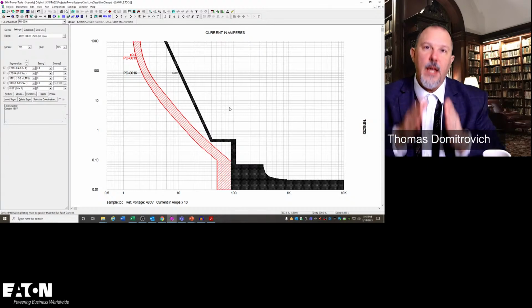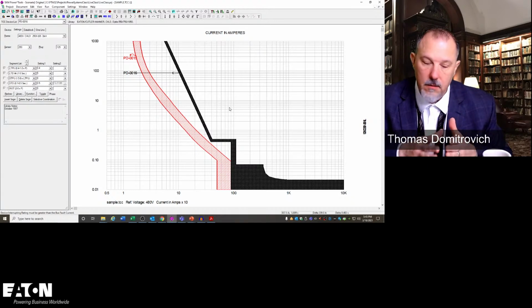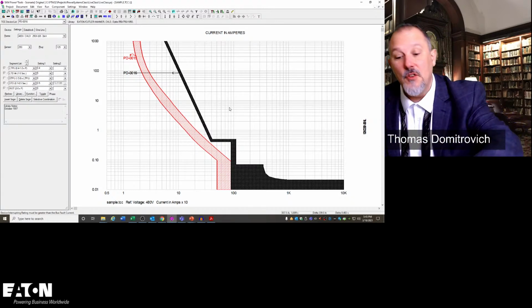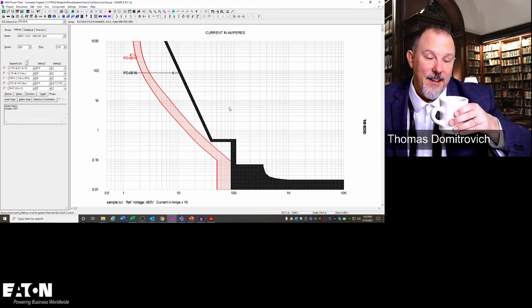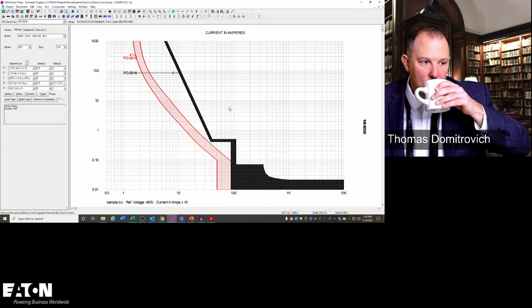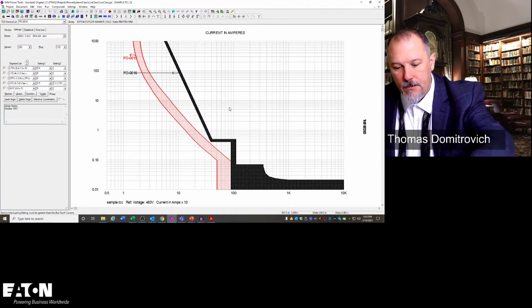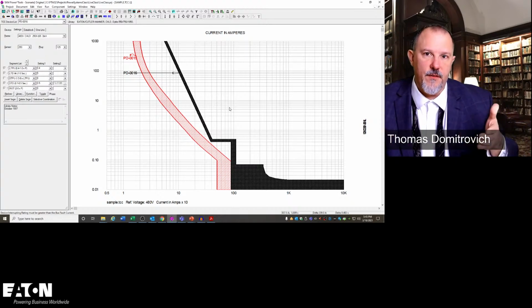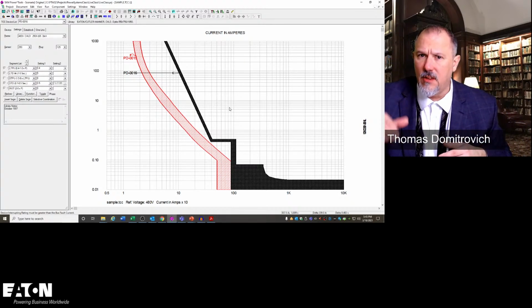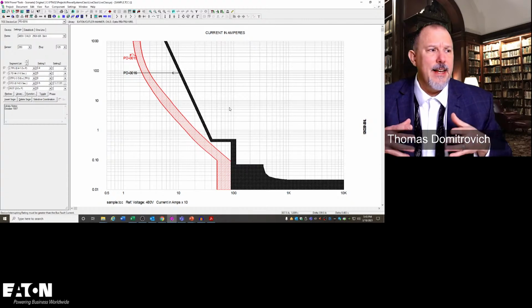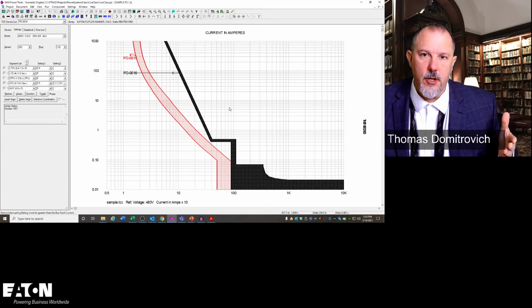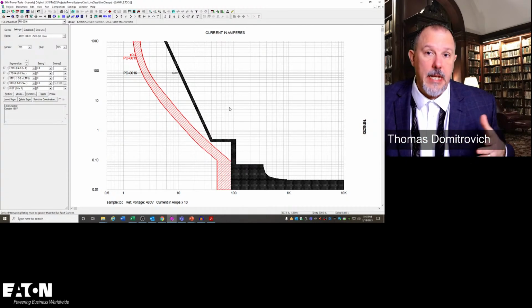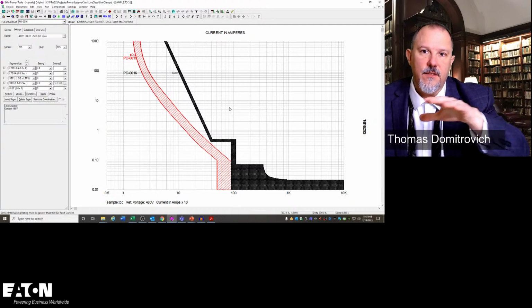Fuses make our lives a lot easier, which is why the breaker guys and the fuse guys argue all the time on this topic. Because all I need to do when I'm dealing with fuses is maintain a 2-to-1 ratio for the most part, but you've got to look at the tables. And regardless of the fault current, always up to 200,000 amps, whatever the interrupting rating is, I know I selectively coordinate.